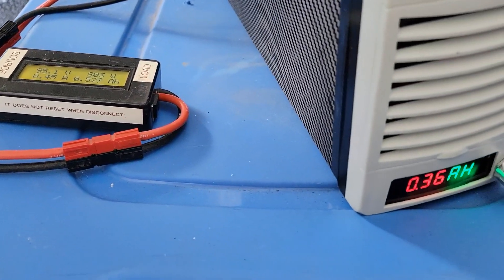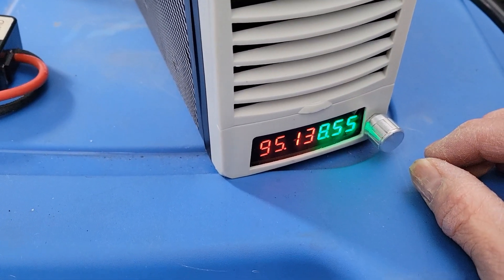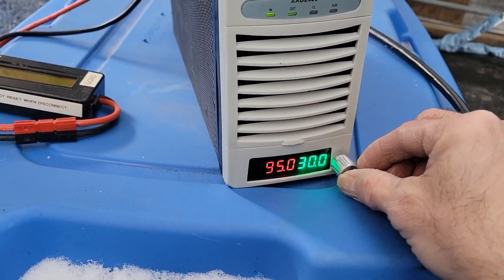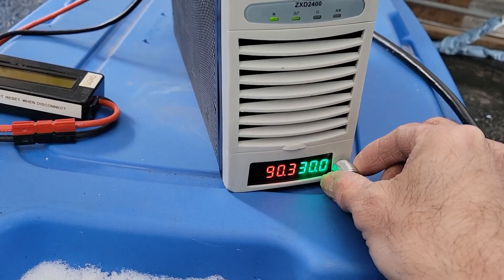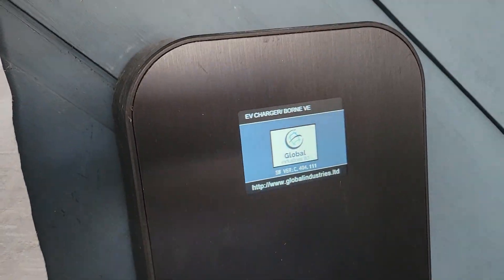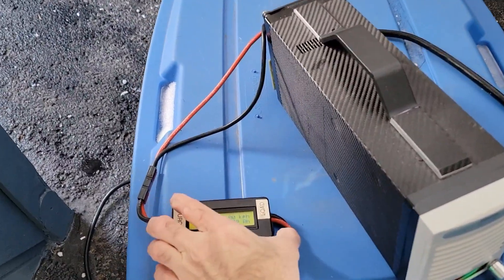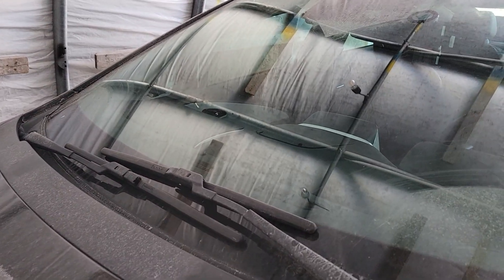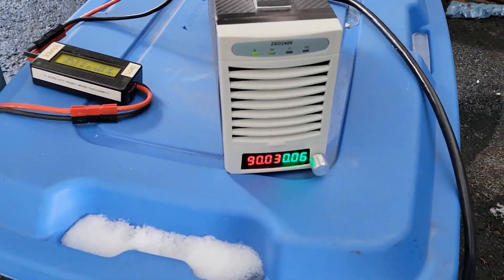Want to try 90 volt? Let's do it. Instead of disconnecting everything, I'll just readjust the voltage to 90 volt and see if it starts again. The relay clicks, yellow light — and nothing. So it won't recharge at 90 volts.